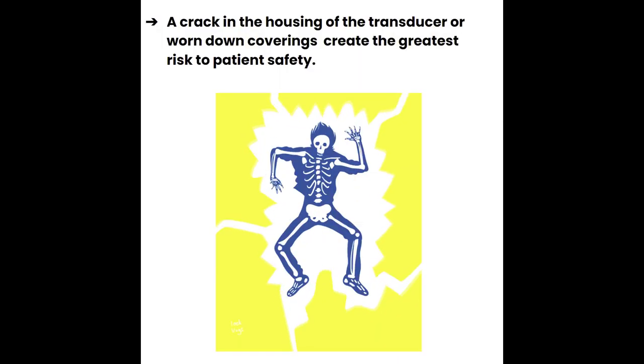In addition to making sure to only use ultrasound as necessary, the sonographer should also make sure that the equipment is in proper working order. Refer back to Unit 22 Quality and Performance for more guidelines on quality assurance. Now the machine can be a source of electrical and mechanical hazards as well to the patient. In fact, a crack in the housing of the transducer or worn down coverings creates the greatest risk to patient safety. Electrical shock can occur if the transducer integrity is diminished.